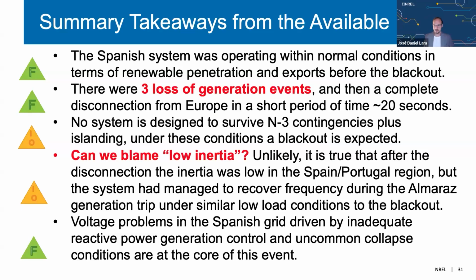Can we blame low inertia? Well, the data that we have now shows that it's extremely unlikely to be low inertia. Because even though the inertia was low, after the disconnection the system was also able to recover from the Almaraz event with no problems on the inertia side. And one of the things that we know now is that voltage problems in the Spanish grid were driven by this inadequate reactive power generation control.